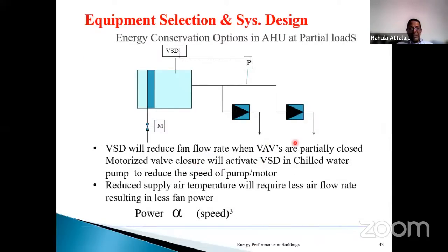I have discussed this kind of VSD that can be used in the air handling unit, the cooling coil, and also incorporating the variable air volume systems, as I showed in the beginning, using a static pressure sensor to control the VSD of the supply fan of the air handling unit. So just note that the power consumed by a blower or a fan varies with speed to the power 3, so a small variation in speed can reduce the power by a large amount.